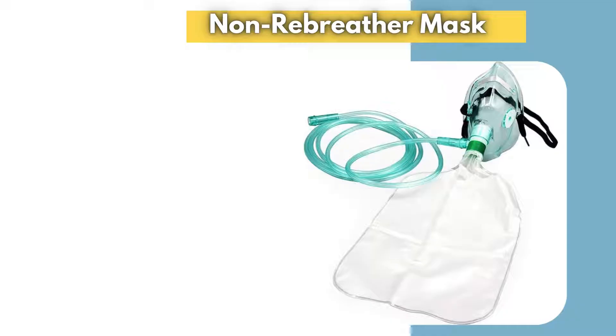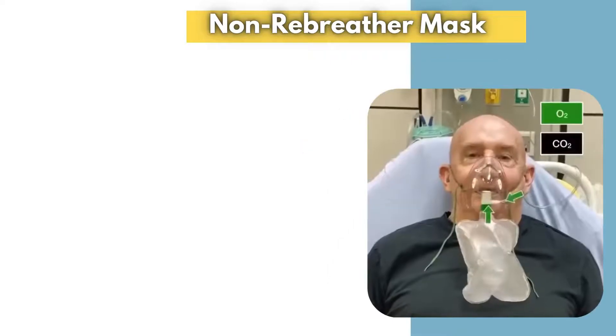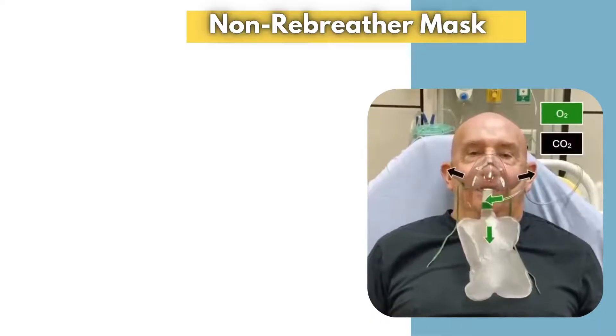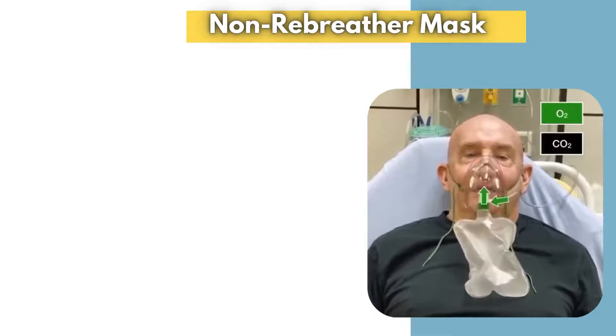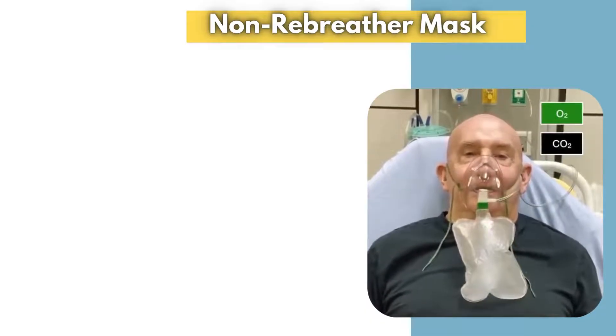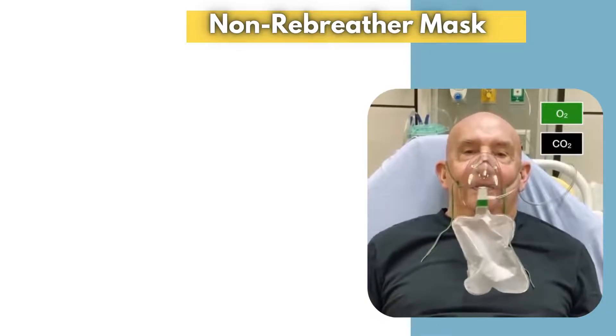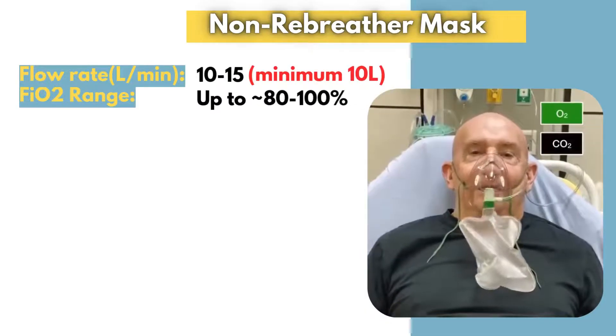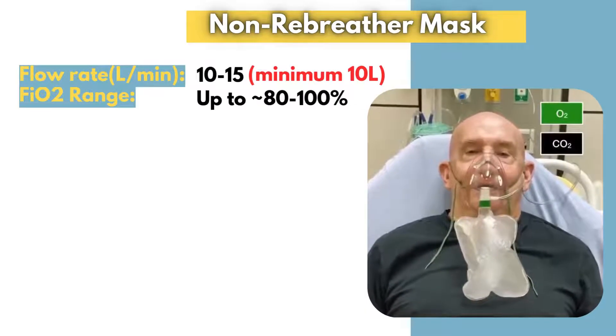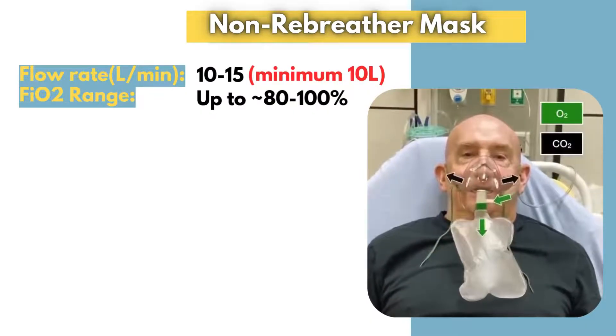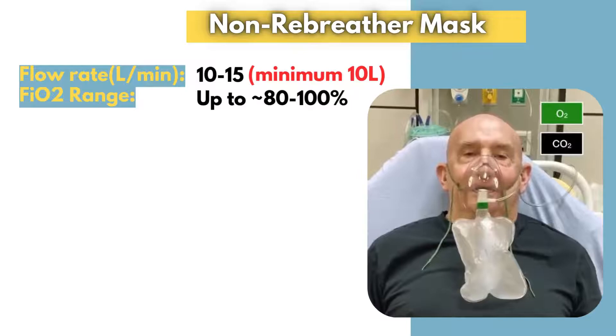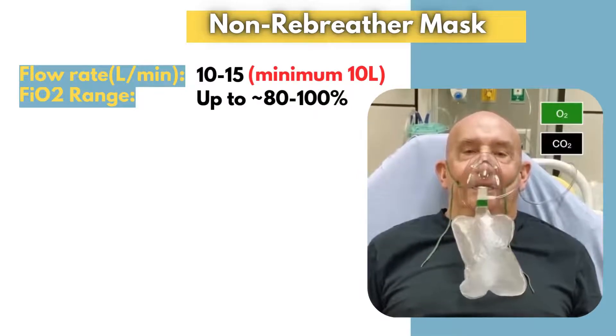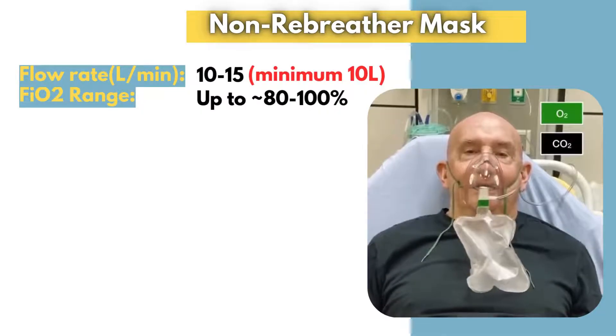The non-rebreather mask is a high-concentration oxygen delivery device consisting of a face mask attached to a reservoir bag filled with nearly 100 percent oxygen. It features two one-way valves — one over the reservoir bag and another over the exhalation ports. These valves allow carbon dioxide to escape while preventing room air from entering during inhalation, ensuring that the patient receives a high fraction of inspired oxygen. The flow rate ranges from 10 to 15 liters per minute, delivering an oxygen concentration of approximately 80 to 100 percent. The minimum required flow rate is 10 liters per minute to keep the reservoir bag inflated and ensure adequate oxygen delivery.